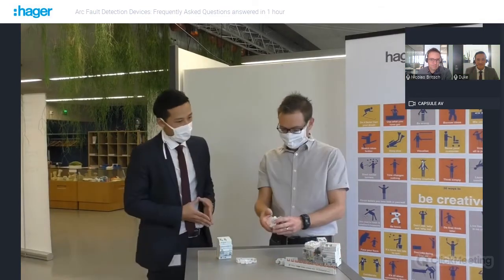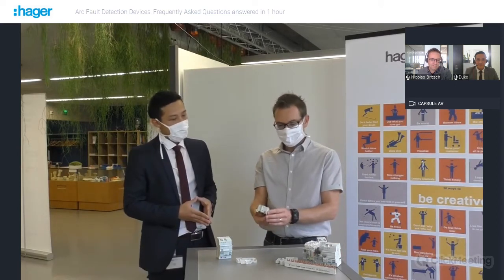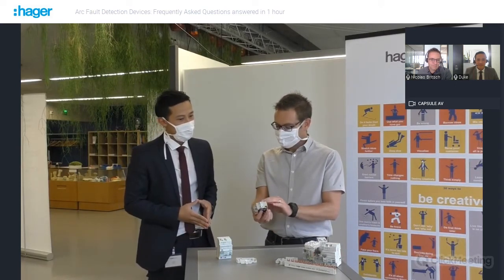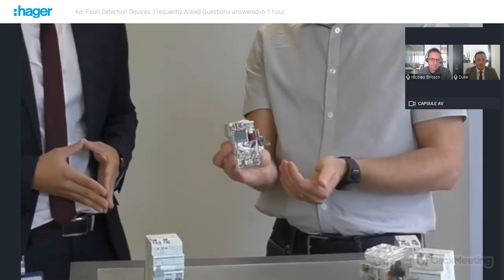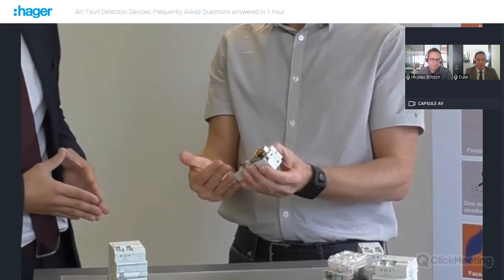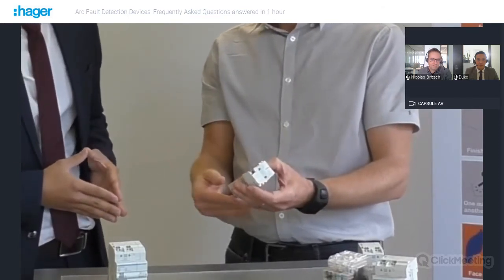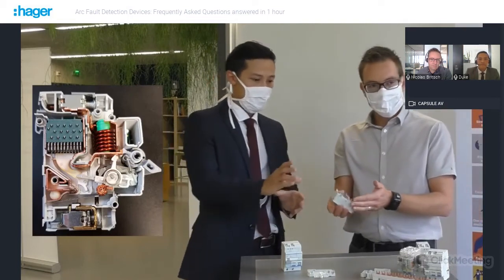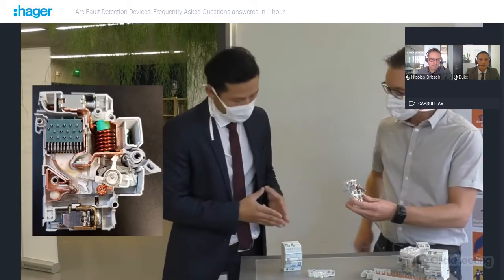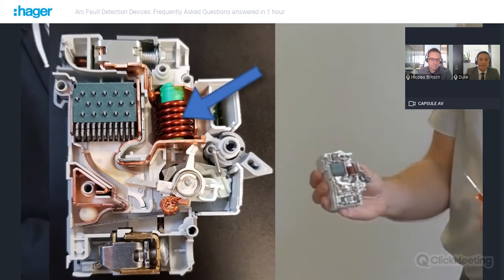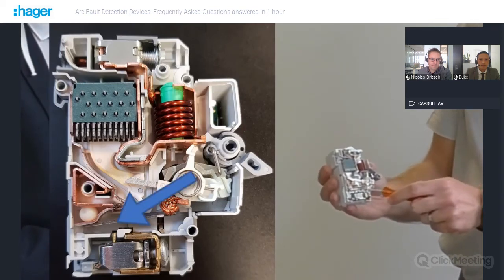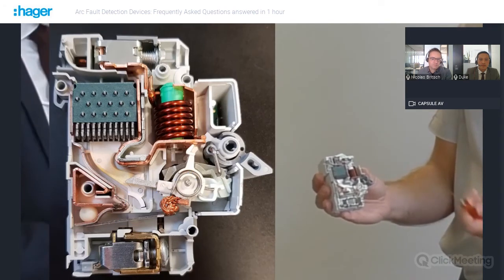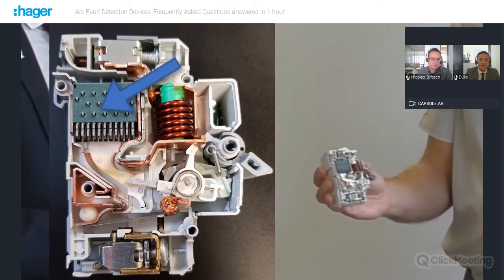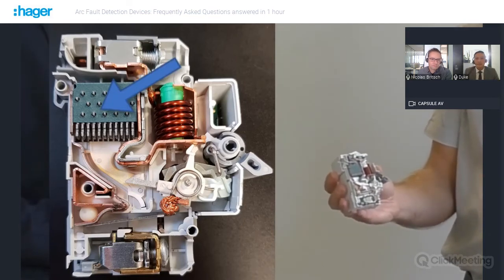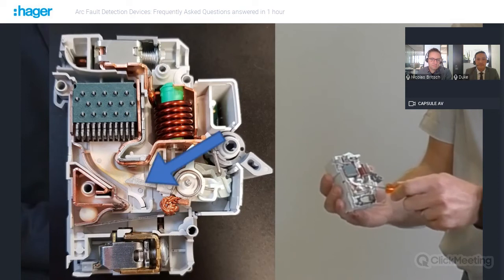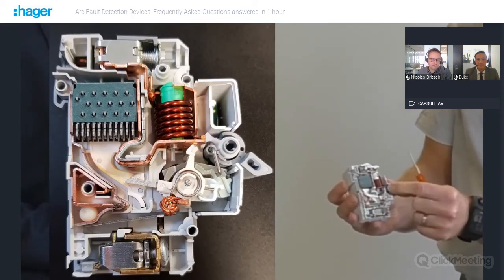Whoa, unbelievable. So here we have the product which is opened, and as you can see, we have two parts, two sides. The left side is the MCB side, and the right side is the arc fault detection side. On the left side, the MCB side, you will see conventional electromechanical parts. First, you have the magnetic coil for short circuit protection. You have the bimetal here for thermal protection in case of overload. You have the arc chamber in case of short circuit to extinguish the arc. The terminals, and of course the contact here, which will close if I close the handle.